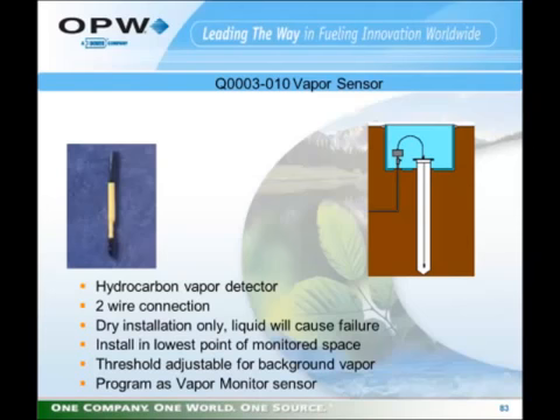The Q0003-010 vapor sensor. It's a hydrocarbon vapor detector, 2-wire connection, dry installation only. Any installation in liquid will cause it to fail. Normally installed in the lowest point of a monitored space because hydrocarbon vapors are heavier than air and would tend to sink to the lowest portion of the space.